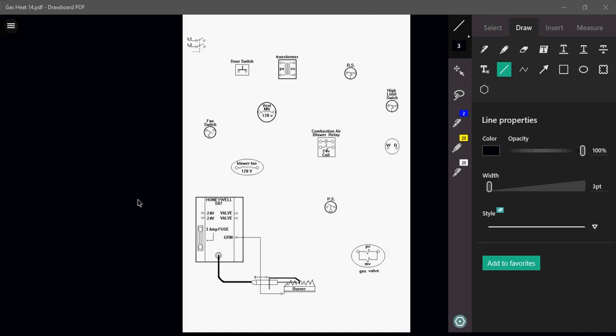That motor is used to remove any sort of leftover combustible gases that may be still stuck inside the heat exchanger, so that we don't have a reaction or a bad light off. It's also there to help push your flue gases through the heat exchanger as the furnace is actually lighting off. But it also, almost in some ways, can act like a safety.